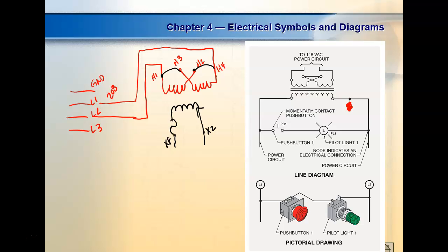The L1 and L2 for our motor control circuit is 120 volts, so around 117. But the transformer is an industrial transformer, so in a transformer, the one with the highest leads are called the high side. The one with the smaller number of loops is called X. They don't call it L for low because L is reserved for inductors, and they don't want you to get confused. So the transformer's labeled X1, because this right here is actually X1.